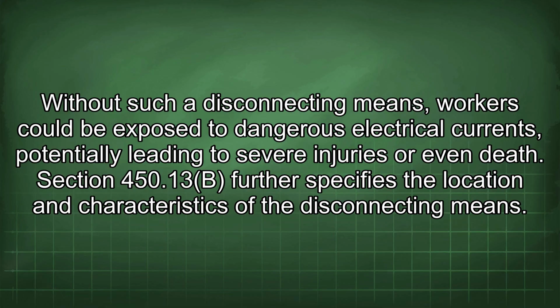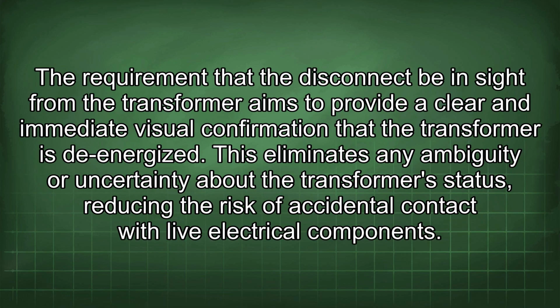Section 450.13b further specifies the location and characteristics of the disconnecting means. The requirement that the disconnect be in sight from the transformer aims to provide a clear and immediate visual confirmation that the transformer is de-energized. This eliminates any ambiguity or uncertainty about the transformer's status, reducing the risk of accidental contact with live electrical components.